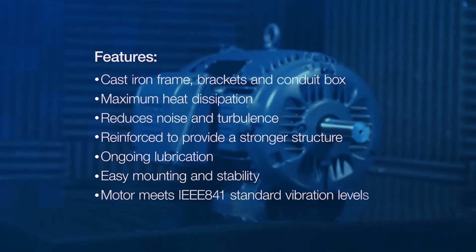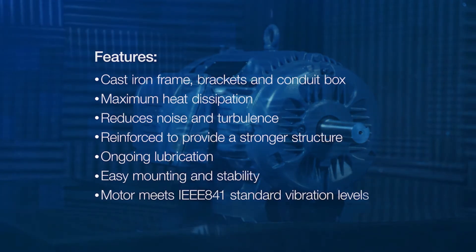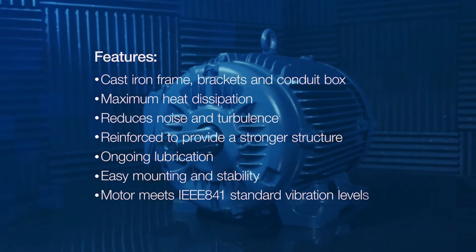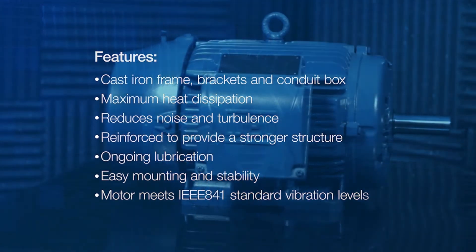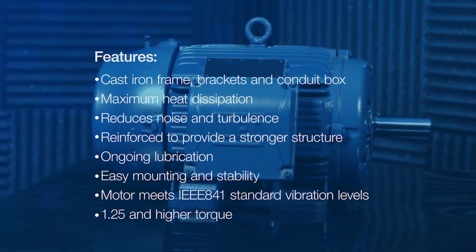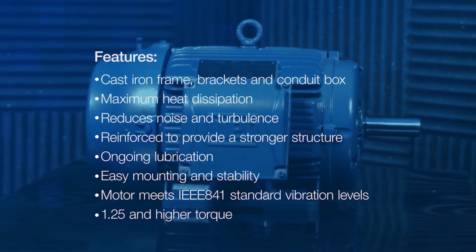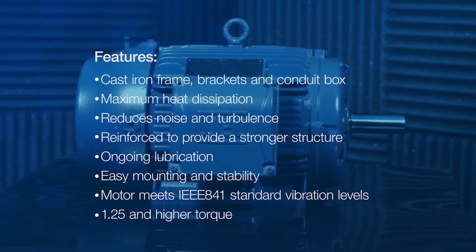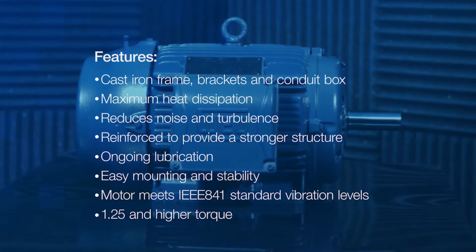In addition, motors are balanced to 0.08 inches per second, meeting IEEE 841, which is one of the toughest standards in the industry. With a higher service factor than its competition, 1.25 at 100 horsepower and below, combined with high torque, W22 motors are designed for power and strength.